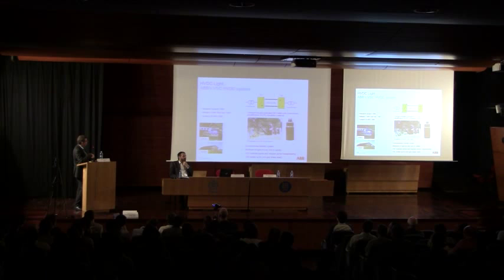And originally with the HVDC light concept we were only using cables with plastic insulation. So we are using cross-linked polyethylene insulation material. And the good thing with this kind of cables is that they are very light. So you could see here a picture where we are plowing down the cable into the ground. And the cables do not contain oil, so we'd say it's an environmentally friendly system. And it will be, of course, a minimum right of way due to its underground cables.